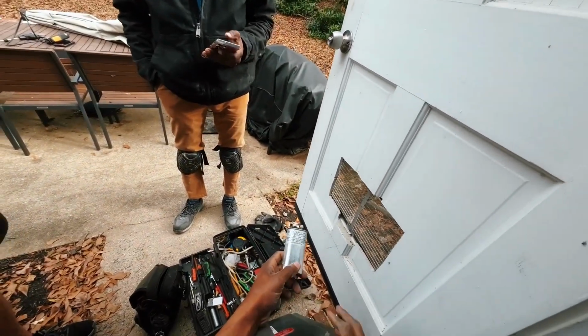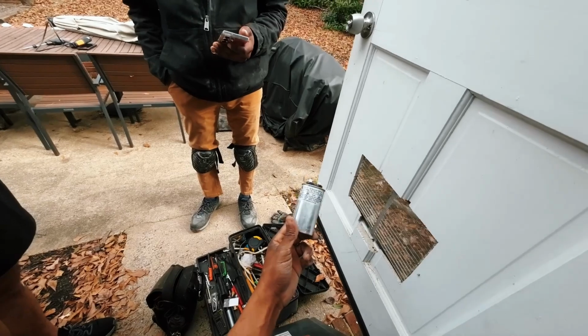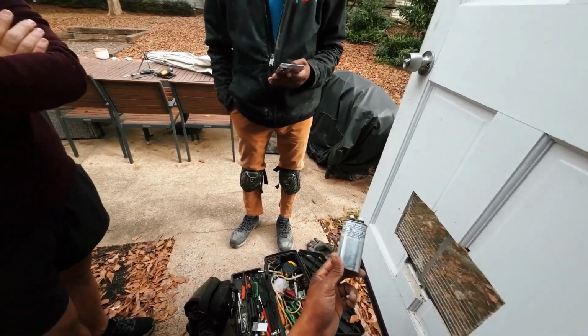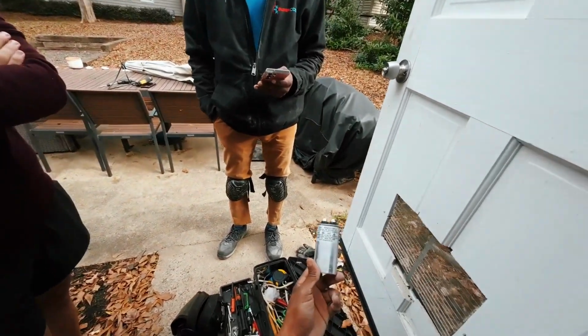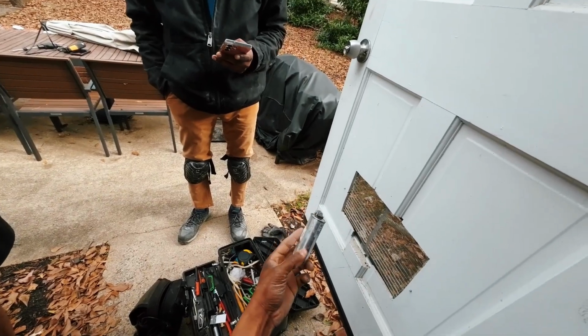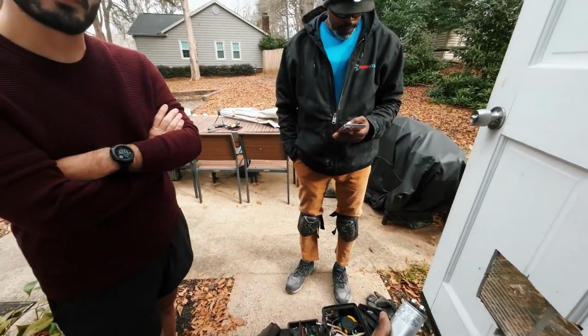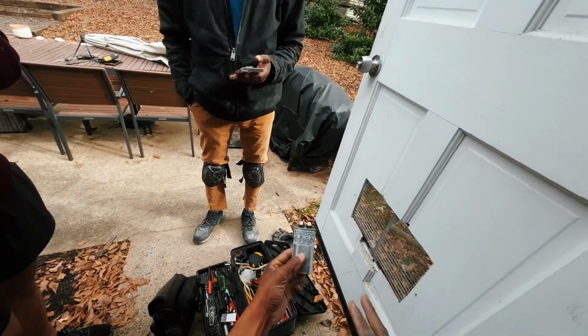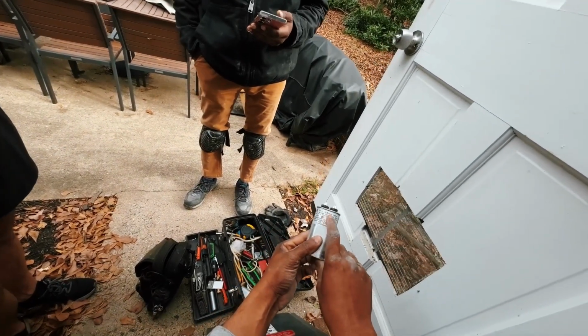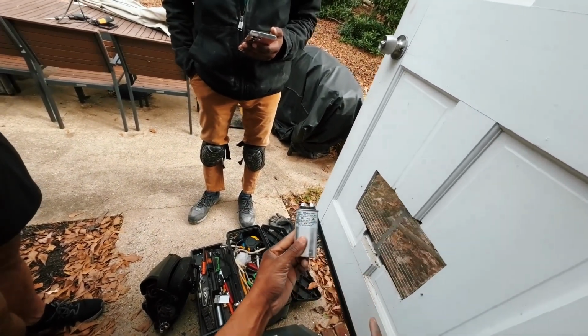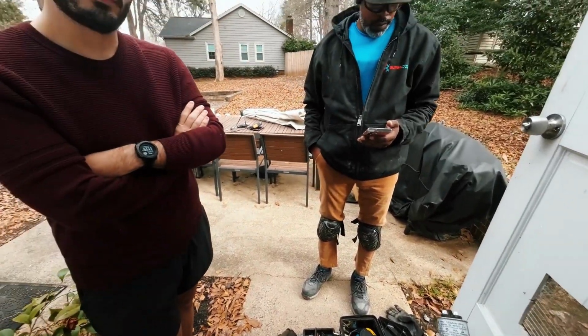So this is a consumable item - it basically holds a capacitance, almost like a battery holds a charge. As these get weaker, it's still running, but the manufacturer says plus or minus 5%, so this thing's probably time to get replaced at that point.